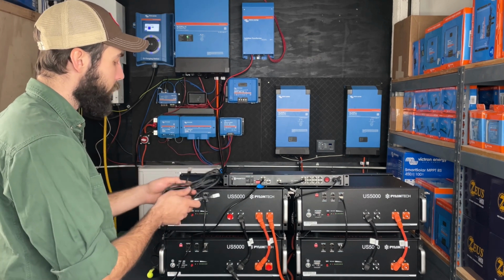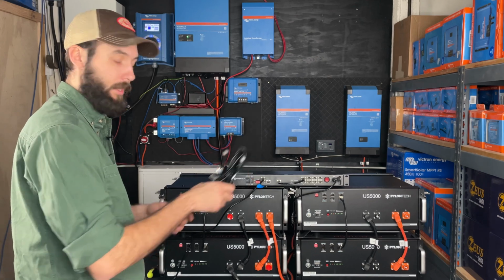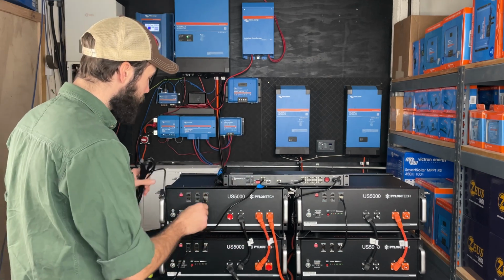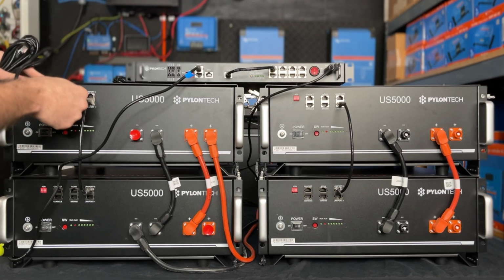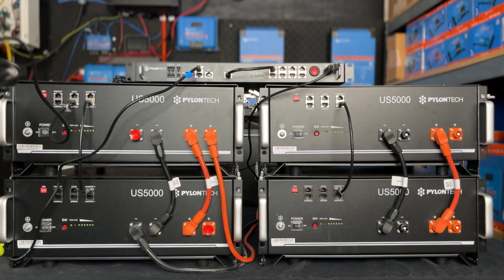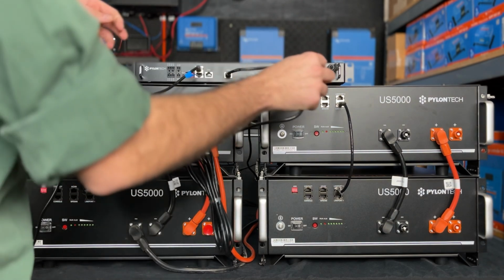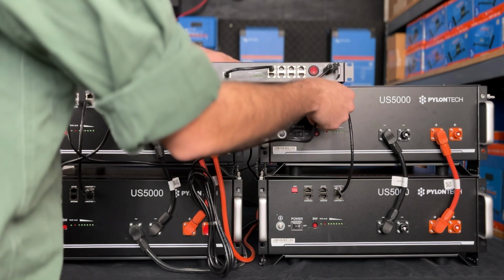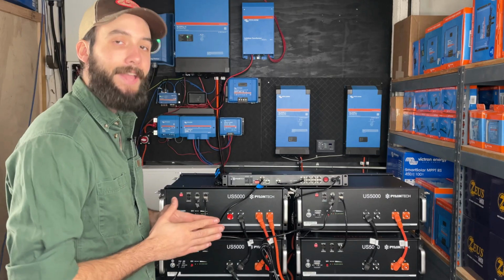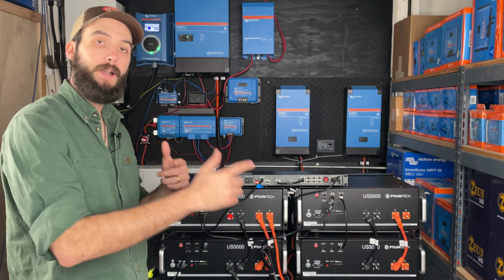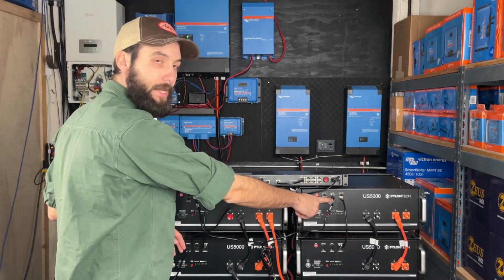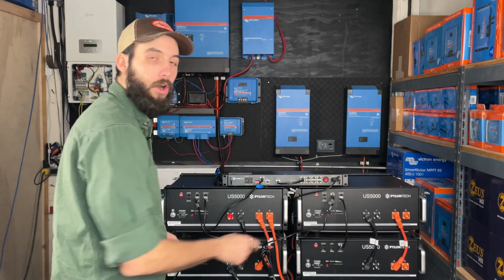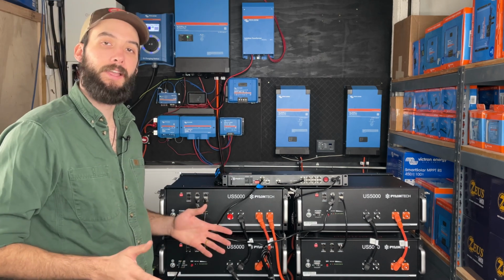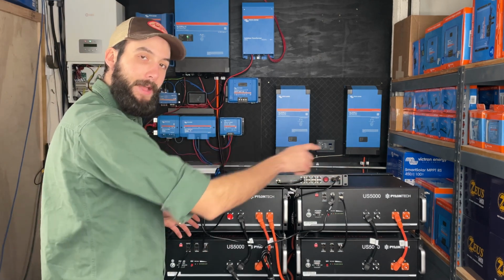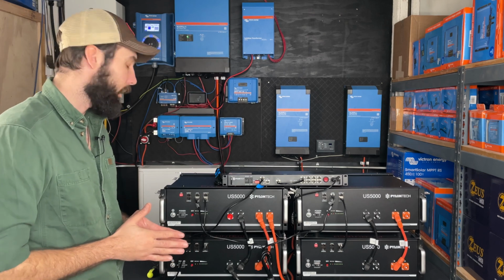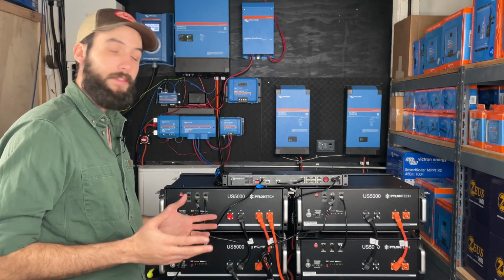We take this longer battery-to-battery communication cable and plug it into the B, RS-485 on this master battery, and then over here into the ACAN port on the other master battery. If we had subsequent stacks, we'd go down the line plugging from B to A, all the way down until every stack is hooked up, master battery to master battery. Now that's taken care of, we can go about turning on these batteries.